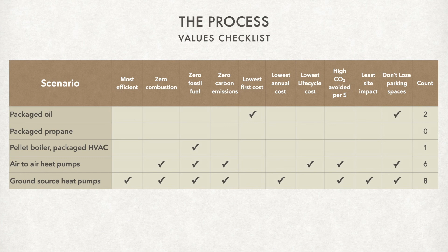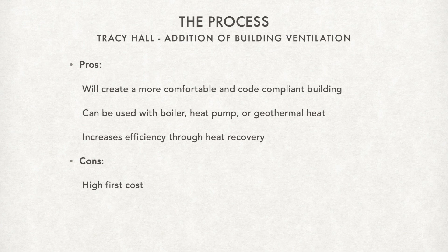So for Tracy Hall, this addition of adding building ventilation, for a more comfortable and code compliant building, the ventilation system itself doesn't care what heating system is used. We could build a ventilation system for whatever heating system, so those two things aren't exactly tied together. It would be a heat recovery ventilation system, so some large fraction of the heat going out in the exhaust air would be recaptured and put into the incoming air. These systems do cost money, it's an expensive retrofit to Tracy Hall.